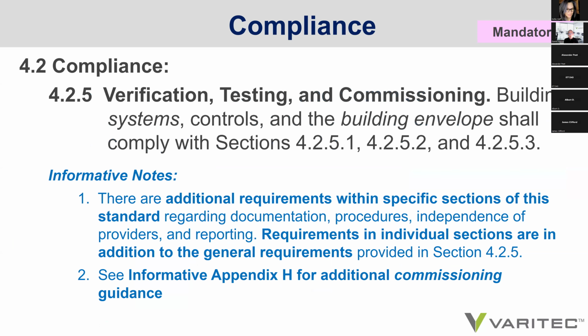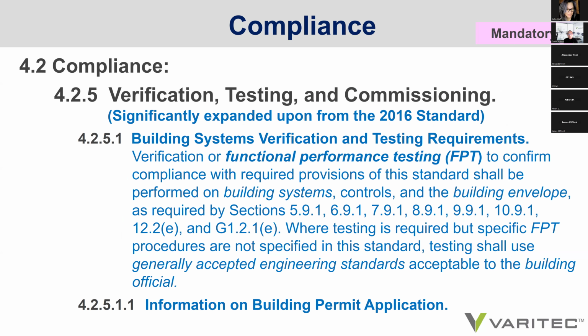And there is now language for verification, testing, and commissioning. Commissioning now is part of 90.1. And there are additional requirements within the section inspections for each section, 5, 6, 7, 8, that addresses requisite commissioning procedures to validate the installation and performance of the various building components. There is also an informative Appendix H for additional commissioning guidance.